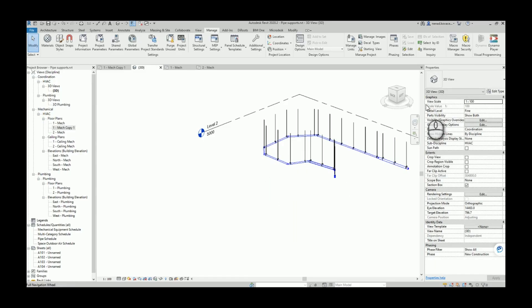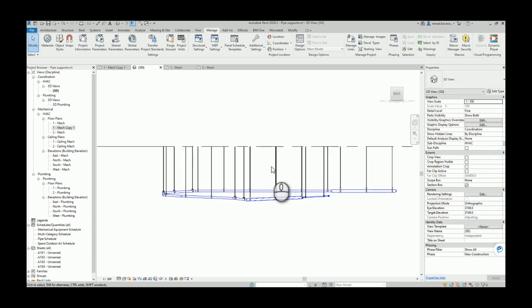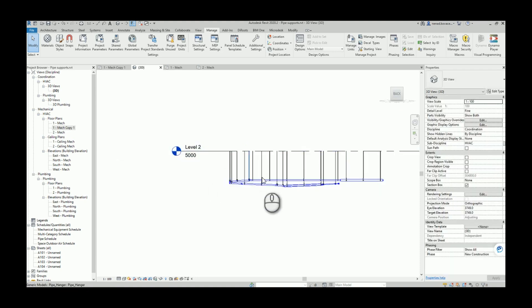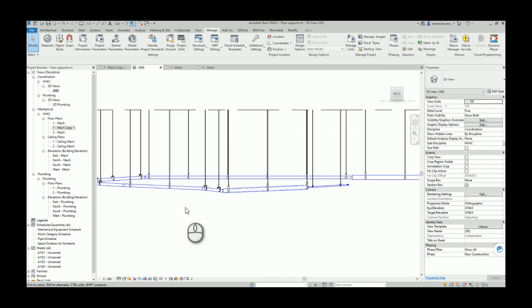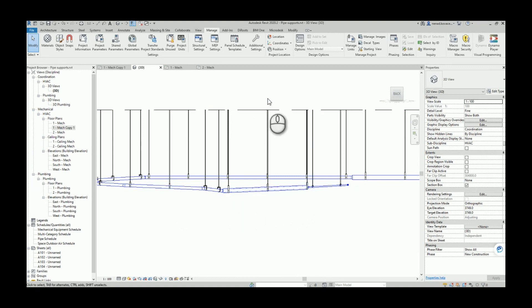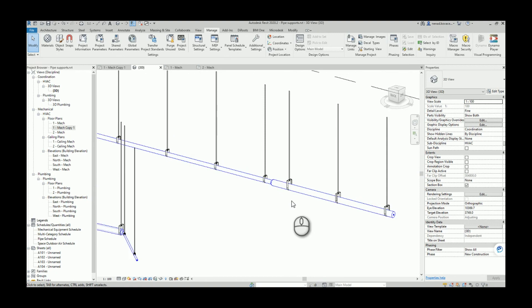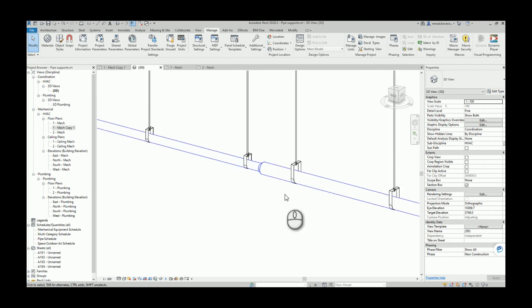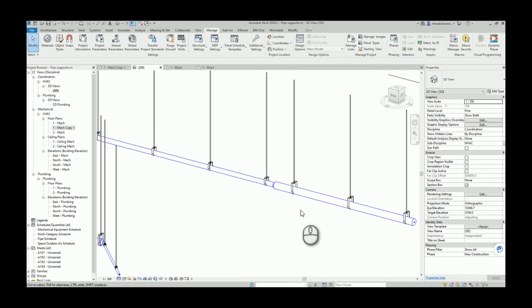First of all, let's see if that elevation is correct — here all hangers go to that 5000 elevation. Note that here we have a change of the pipe height, so even when you're using slope, everything will go to the elevation which you entered. Now if we take a look at our straight sections, our pipe hanger automatically adjusts the outside diameter according to our pipe.